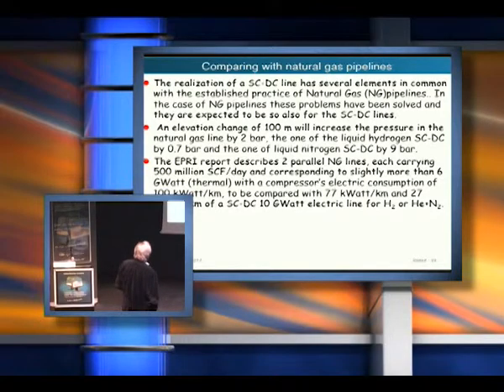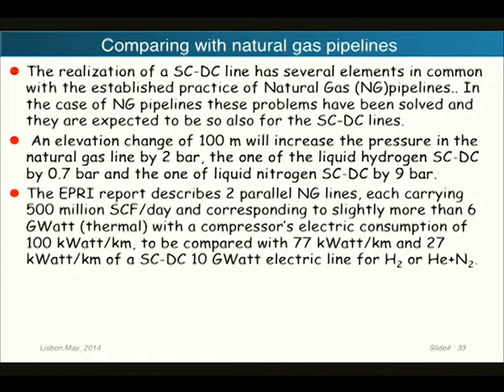The EPRI report, for instance, described 2 parallel natural gas lines, each carrying 500 million cubic feet per day, corresponding to slightly over 6 gigawatts, with a compressor electric consumption of 100 kilowatts per kilometer. This is a line which carries essentially 6 gigawatts thermal per kilometer. It has to be compared with the number I already gave you, which is 77 kilowatts per kilometer, or 27 kilowatts per kilometer for a 10 gigawatt electric line for hydrogen or helium plus nitrogen. So you can see that the consumption for the gas is in fact manageable.